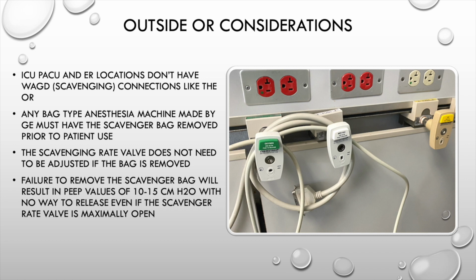All right, so if you get called into the operating room and they need an anesthesia machine to be brought up to an external environment, if you roll the anesthesia machine into an ICU room, these are the connections typically that you'll see. Notice there's no waste anesthetic gas connections like we have in the operating room. So as I said before, any of the bag type anesthesia machine scavenging devices must have the scavenger bag removed prior to patient use. The scavenging rate valve does not need to be adjusted if the bag is removed.